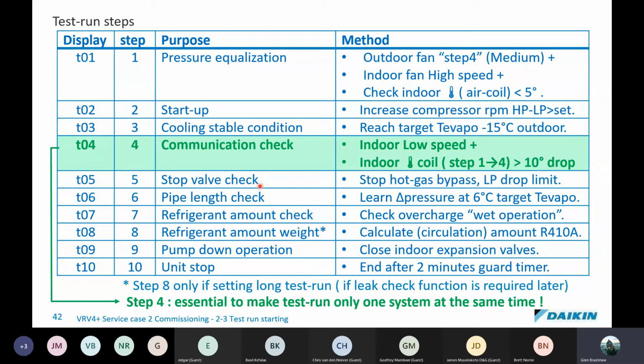T05 is a stop valve check. The hot gas bypass will close, with an LP drop limit. T06 is a pipe length check. Over here it's learning the pressure drop of the system.